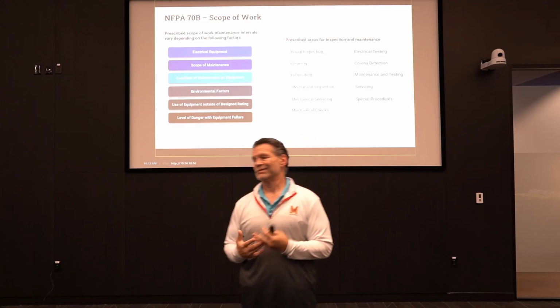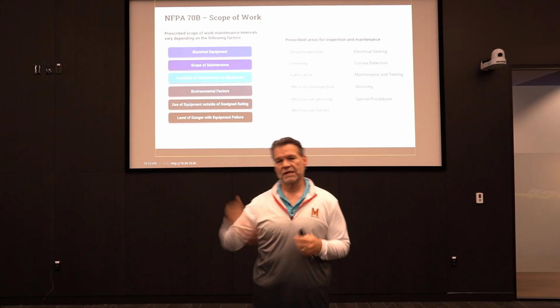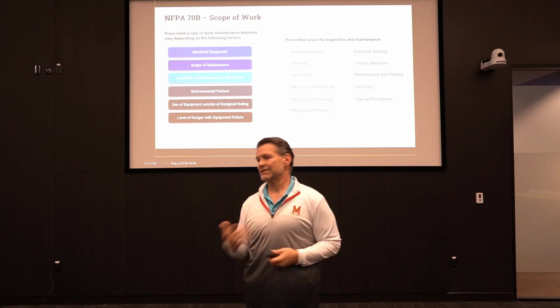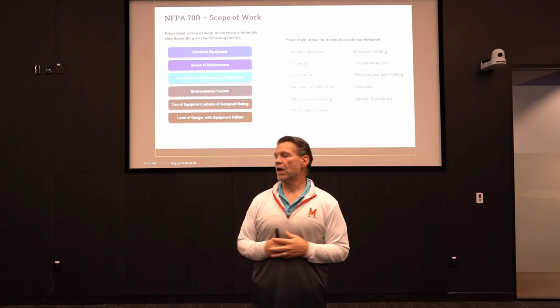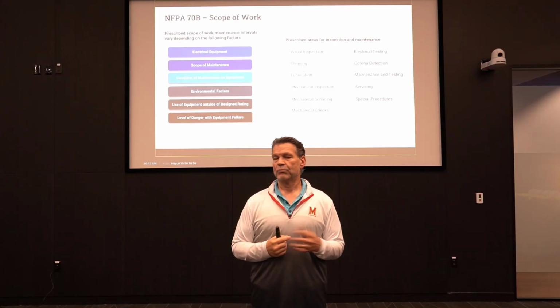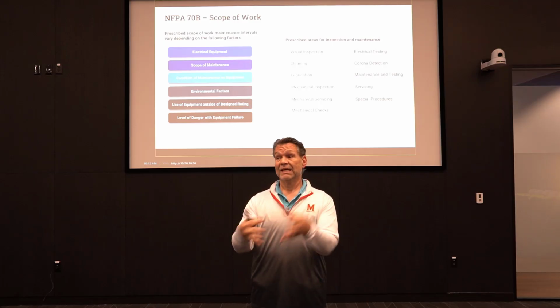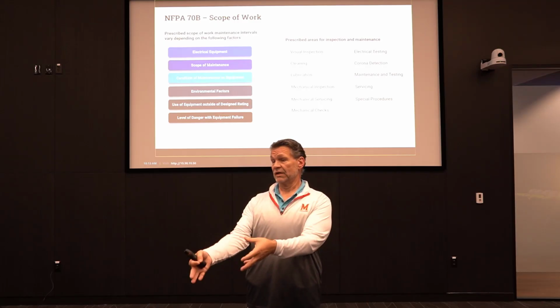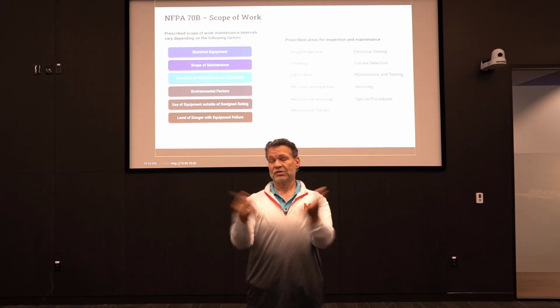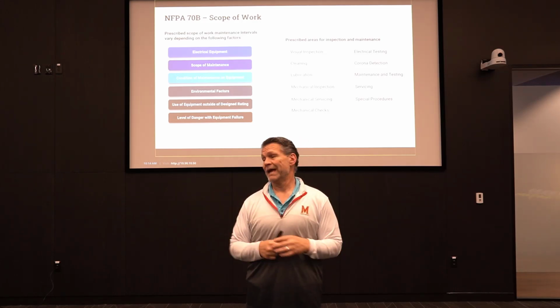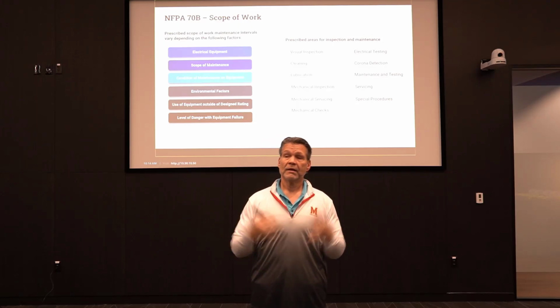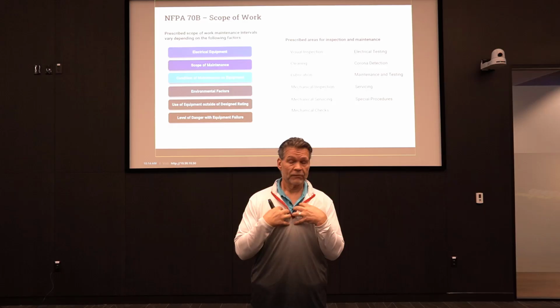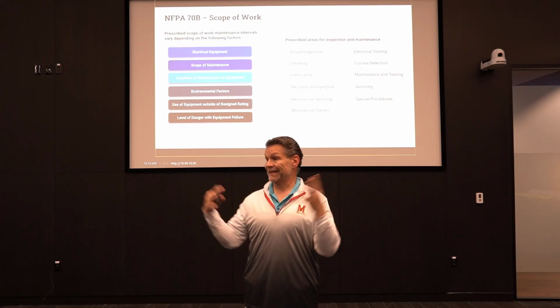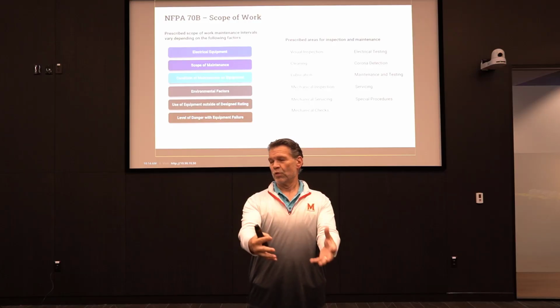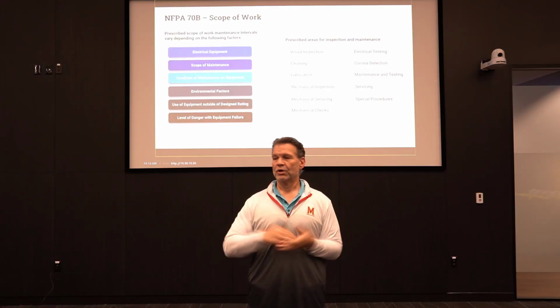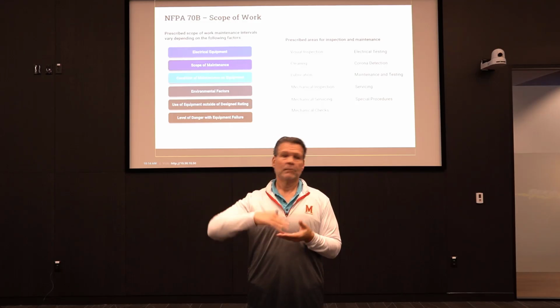Well, if that breaker has never been maintained, never been serviced, never been exercised, never been cleaned, never been lubricated, we no longer know that it's going to open at the appropriate time, the time that was listed in the coordination study, the arc flash study, when it was done. So the information on an arc flash label may not even be accurate, and you could put yourself in harm's way thinking that you're protected. Maybe you're wearing an arc flash suit, whatever the proper clothing is for that level of incident energy, and then it doesn't work correctly. The incident energy is no good because the breaker doesn't open on time because of a lack of maintenance.